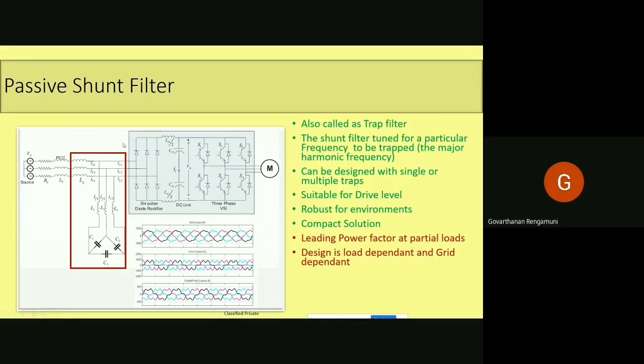The third one is the passive shunt filter. The earlier two techniques can limit the THD only up to 30% to 40%. This will be okay up to a certain level, but if someone wants to meet the IEEE 519 standard, they need to reduce the harmonics much further. So how to do that? The further slides will show some of the mitigation techniques which will help meet the IEEE 519 levels. You can see this is one of the techniques, the passive shunt filter.